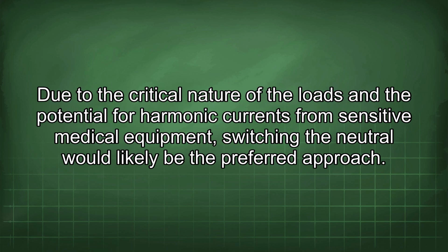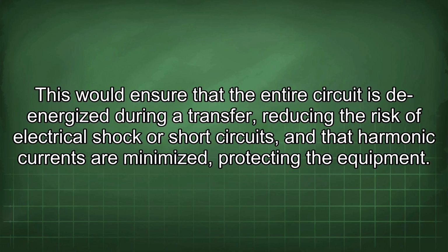Due to the critical nature of the loads and the potential for harmonic currents from sensitive medical equipment, switching the neutral would likely be the preferred approach. This would ensure that the entire circuit is de-energized during a transfer, reducing the risk of electrical shock or short circuits, and that harmonic currents are minimized, protecting the equipment.